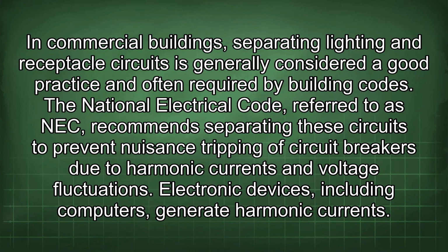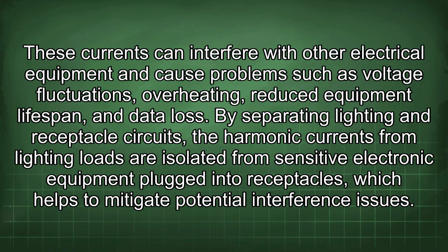In commercial buildings, separating lighting and receptacle circuits is generally considered a good practice and often required by building codes. The National Electrical Code, referred to as NEC, recommends separating these circuits to prevent nuisance tripping of circuit breakers due to harmonic currents and voltage fluctuations. Electronic devices, including computers, generate harmonic currents. These currents can interfere with other electrical equipment and cause problems such as voltage fluctuations, overheating, reduced equipment lifespan, and data loss. By separating lighting and receptacle circuits, the harmonic currents from lighting loads are isolated from sensitive electronic equipment plugged into receptacles, which helps to mitigate potential interference issues.